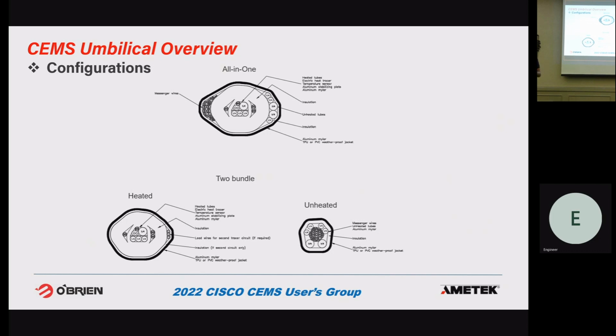Where the 2-bundle approach has its advantages is long-term, over 10, 20, 30 years. All heat trace has a finite life, maybe 5, 10, or 15 years, but at some point it will fail. With an all-in-one, you're replacing the large tubing bundle along with a lot of extra things that are still good, like tubes, wires, and cables. It's just the heat trace that doesn't work anymore. That's when the advantage of the 2-bundle approach comes into play, because the tubing stays in place and you're just replacing the heated portion.